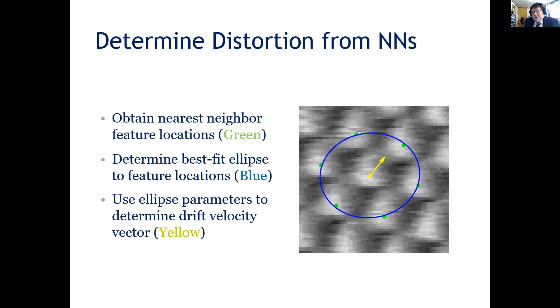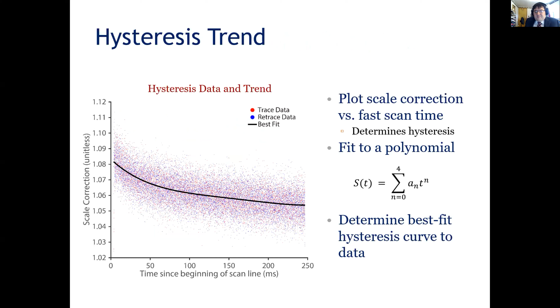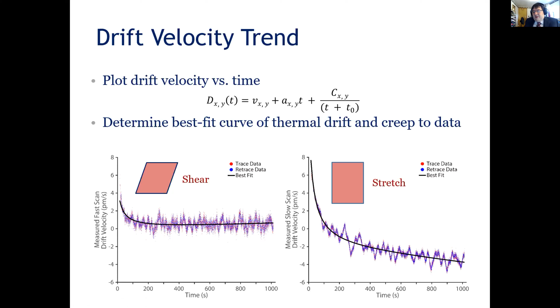We can plot that versus time and get a trend line for that, and there's the distortion that's affecting our image. This is scale correction versus fast scan time, which is a fit for hysteresis. We used a fourth degree polynomial as a model for our hysteresis, which fit pretty well to the data. Then we also have fast scan drift velocity, which causes shear, and slow scan drift velocity, which causes stretch. We fit those to our data using some models for drift velocity and creep with a tiny little bit of acceleration, and that also fits excellently.